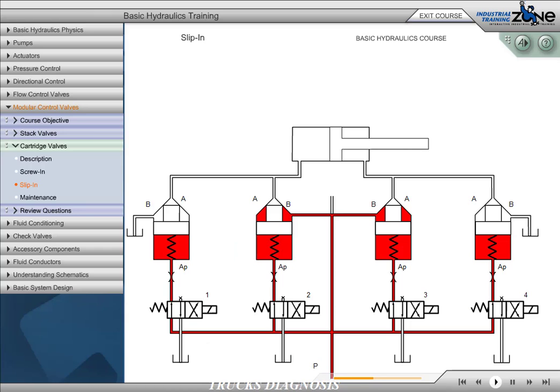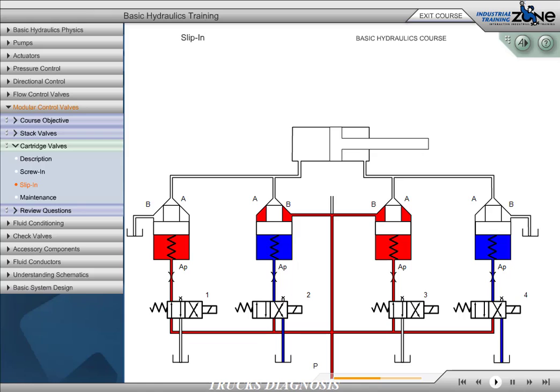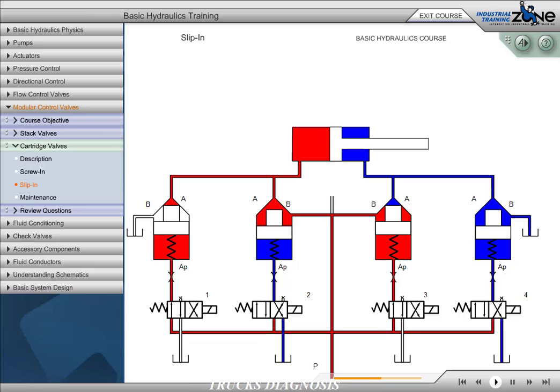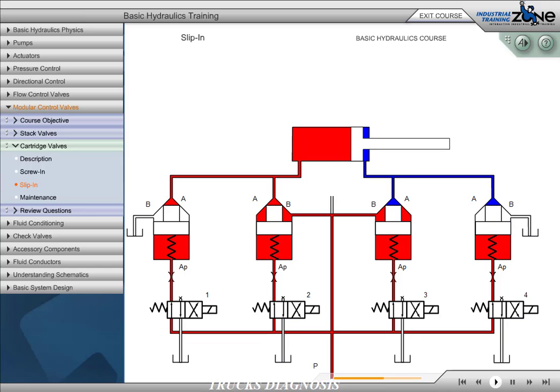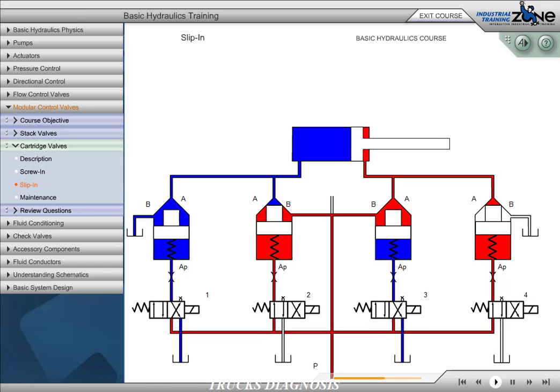This schematic represents a cylinder being controlled by four slip-in cartridge valves, each of which is controlled by a directional control valve. By actuating or deactuating the directional control valves in different combinations, 12 potential flow-path combinations are possible. Energizing valves 2 and 4 will allow flow from the P port to the A port, and return flow from the B port to the T port, so the cylinder will extend. Energizing valves 1 and 3 will allow flow from the P port to the B port, and return flow from the A port to the T port, so the cylinder will retract.